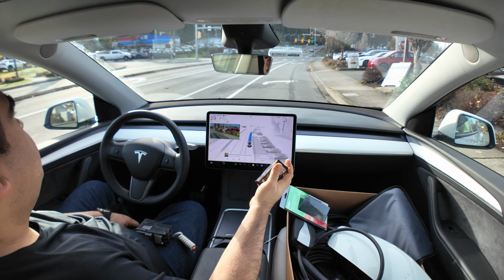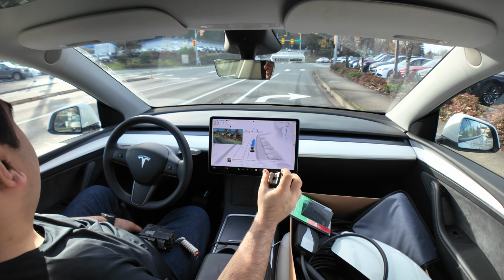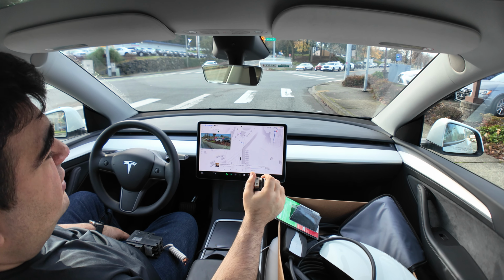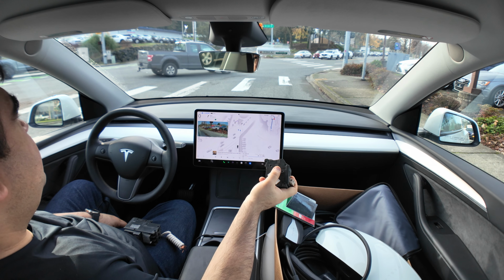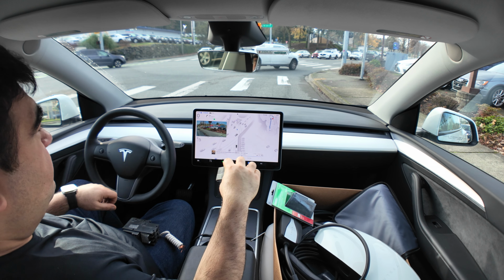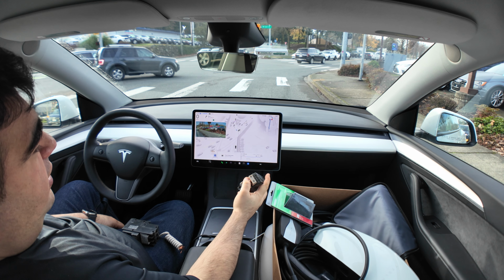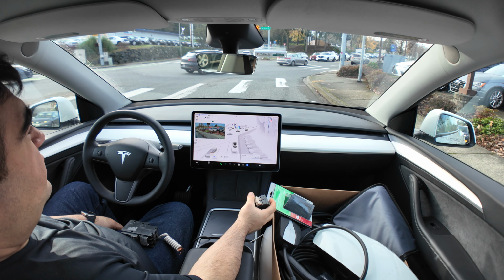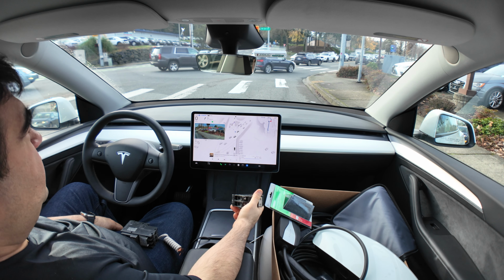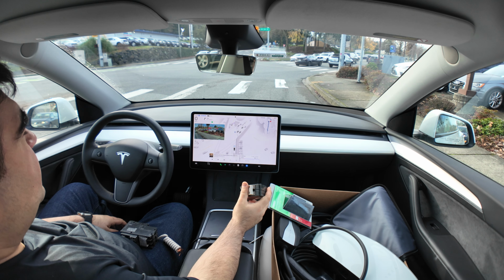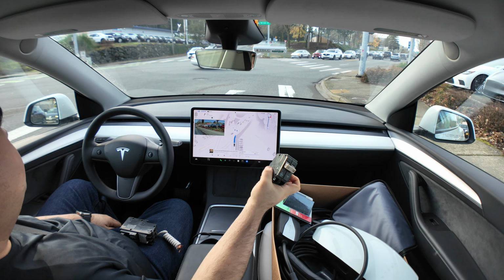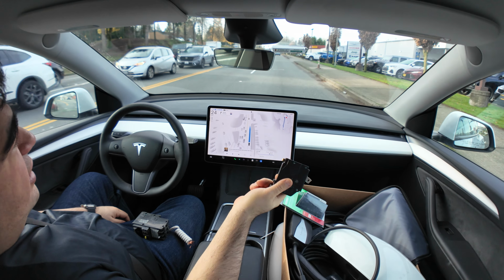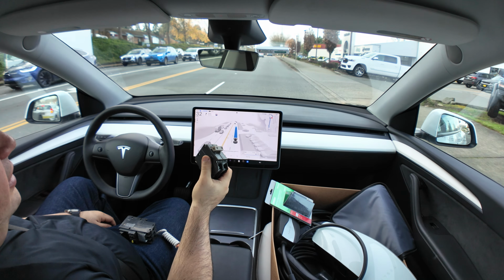But a lot of times you will notice that most people don't actually need the 48 amps charging, and it is much more advantageous or cost effective to put it in as a 40 or a 50, because sometimes you can use the Romex or the flexible cables. In addition to that, you may not come back with a voltage calculation that is favorable. So basically we need to upgrade the service. It's very expensive, upgrade the panel. But if we can put it in at a lower amperage that's suitable for your driving condition, well, why not? Why don't we just put in a 40 or a 30?